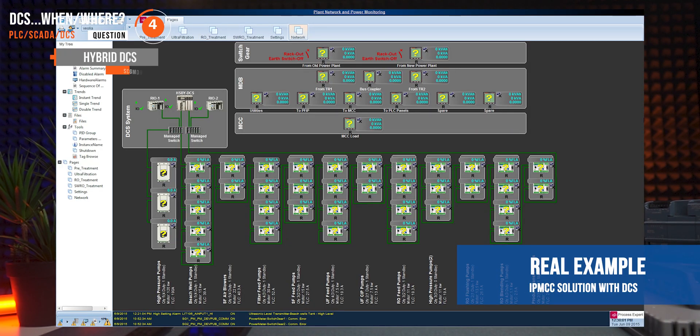The second point where DCS shines is when you have a good amount of communication integration — like hundreds of power meters or starters. DCS will seamlessly create all the communication assignments and functions with a few single clicks, so no mistakes and no overlapping in addresses or communication mapping. But you have to use the same vendor equipment — so with Siemens DCS (PCS7), you have to use Siemens MCCs.